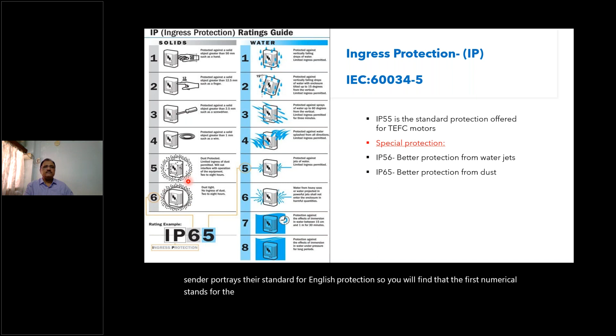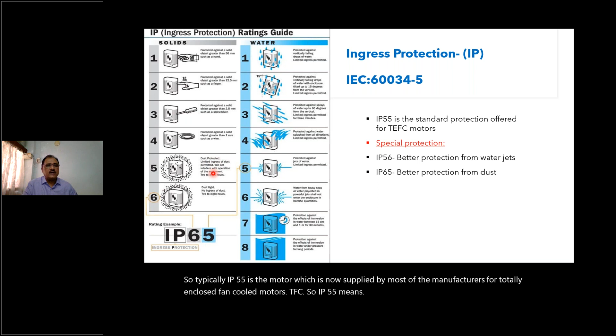So you will find that the first numeral stands for the solids that will enter the motor. The second numeral stands for the water that will be splashing or falling on top of the motor. So typically IP55 is the motor which is now supplied by most of the manufacturers for totally enclosed fan cooled motors, TEFC. So IP55 means powdery dust will not enter the motor. Similarly, water projected by a jet will not enter the motor.